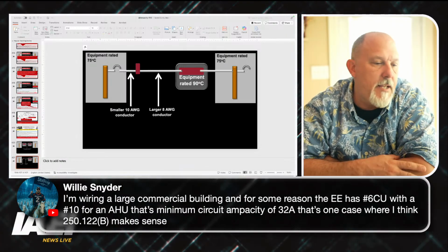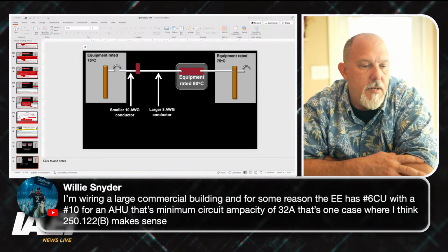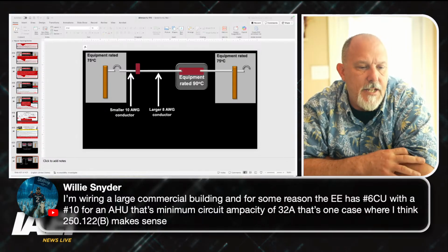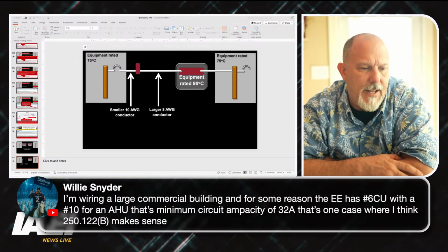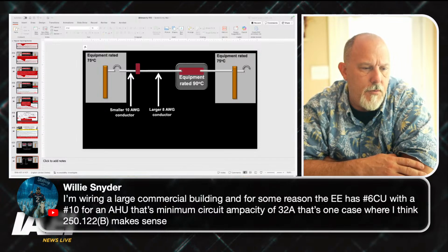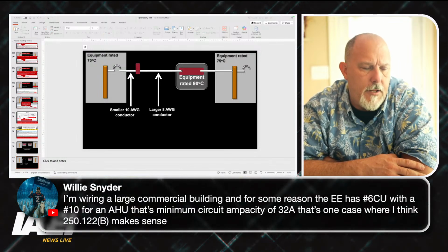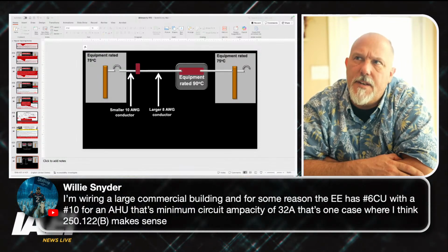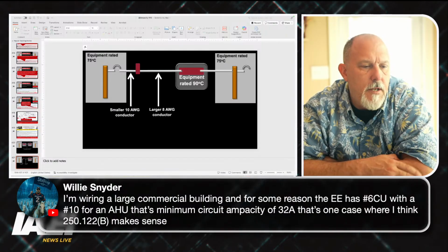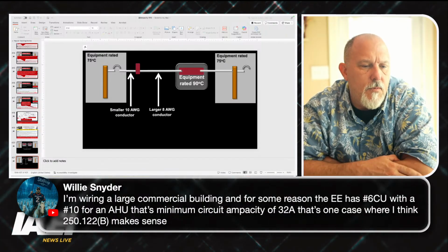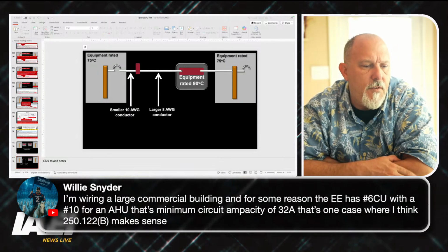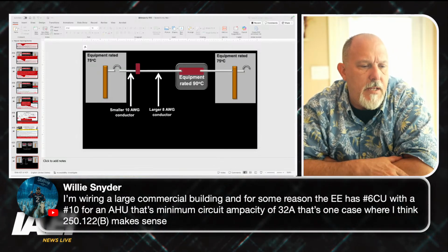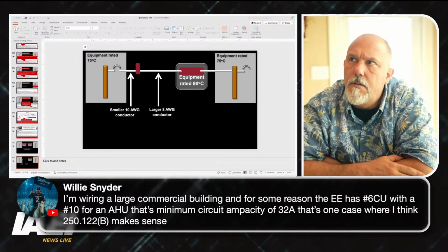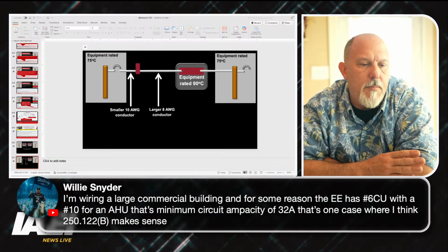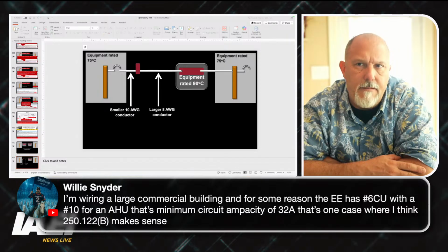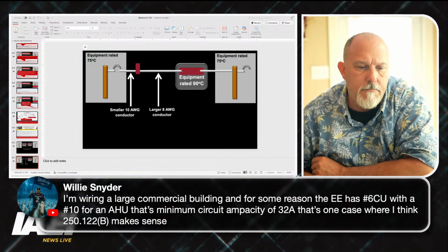If he routed them in the same raceway, that's minimum circuit ampacity, a 6 gauge copper with a number 10 for an AHU. Air handling unit. A 6 gauge copper with a number 10. I'm not sure what that means. 32 amps. That's one case where I think 250.122(B) makes sense. I'm not sure what you mean by a 6 copper with a 10. I'm not sure what that means.